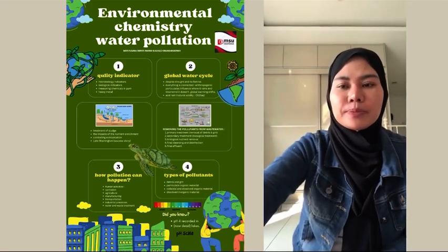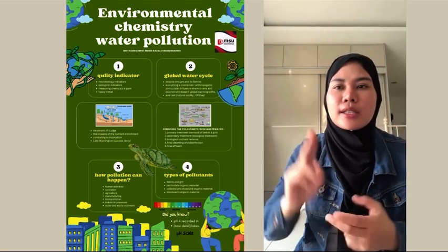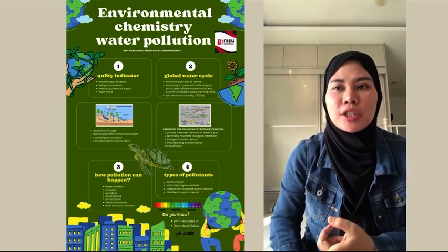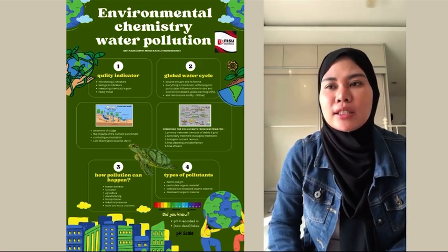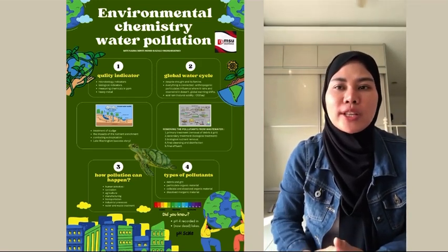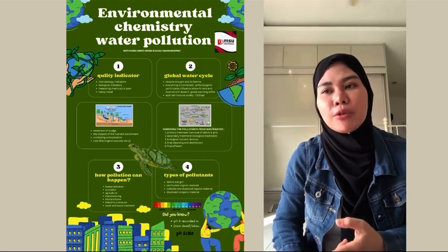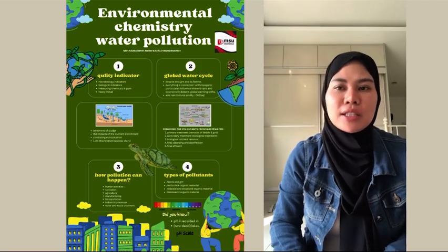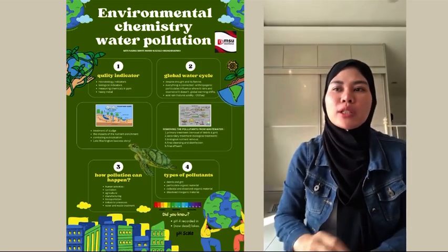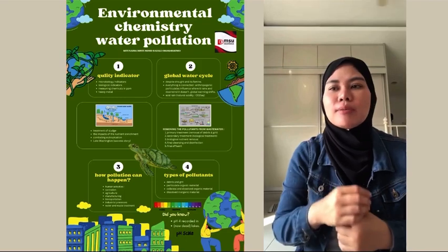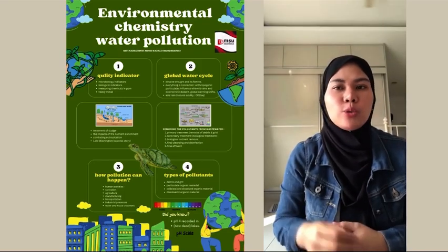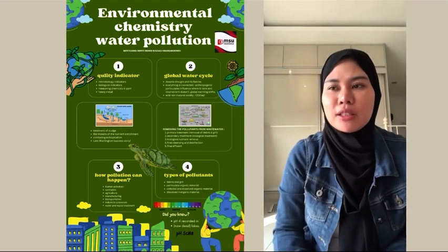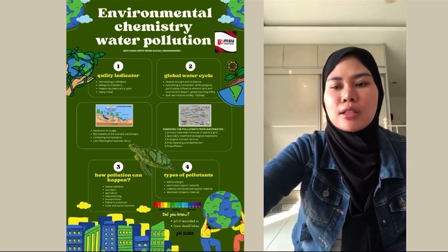incinerator. The second is secondary treatment, biological treatment. It uses organisms, natural decomposers, and detritus feeders. The wastewater from primary treatment is a food and water-rich medium for the decomposers and detritus feeders. Oxygen needs to be added to the water to enhance the organisms' respiration and growth. Two systems are used to add oxygen: the trickling filter system and the activated sludge system.